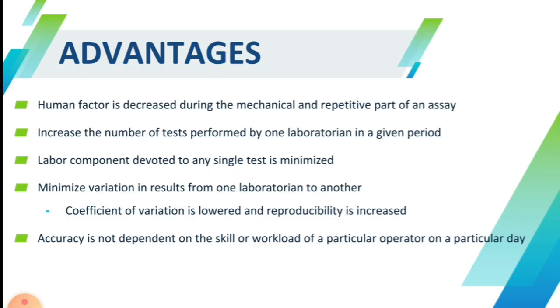Automation, however, cannot correct for deficiencies inherent in methodology. A third advantage is gained because automation eliminates the potential errors of manual analysis such as volumetric pipetting steps, calculation of results, and transcription of results. A fourth advantage accrues because instruments can use very small amounts of samples and reagents. This allows less blood to be drawn from each patient, and the use of small amounts of reagents decreases the cost of consumables. In addition, automation facilitates better space utilization through consolidation.